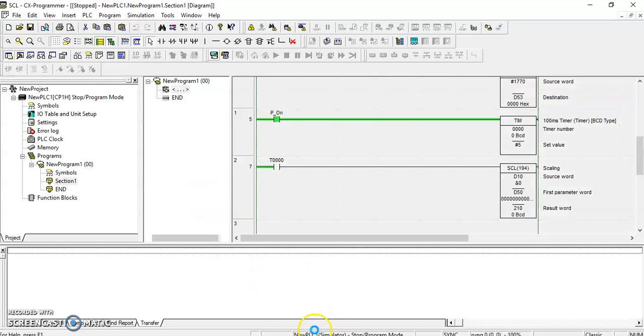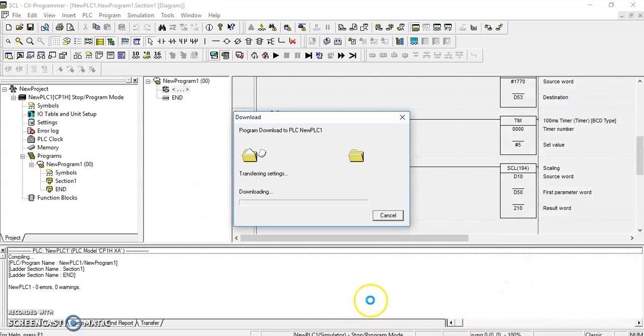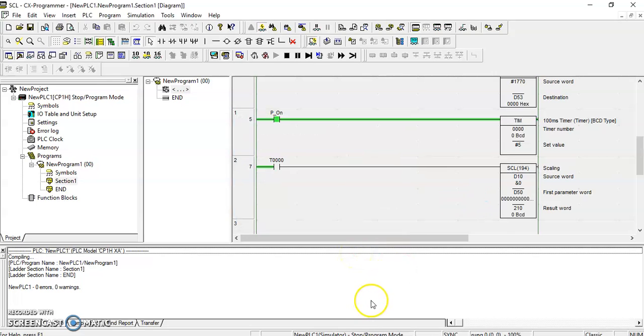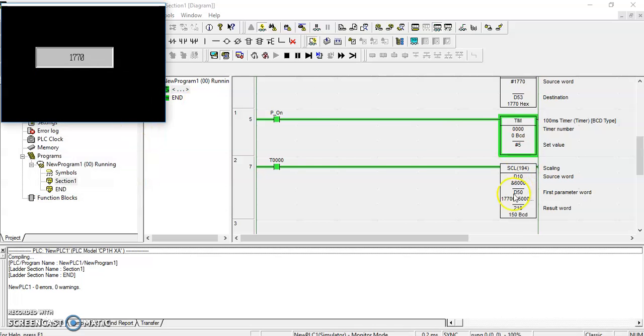So as we wait for it, you can see as a transfer here. I have a 0 value, so it should be 0. This is our minimum input and this is our minimum output. So considering we need 170 degrees Celsius, enter. It should result to 150 BCD.